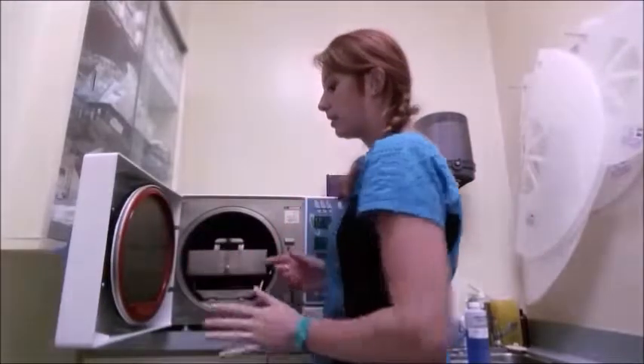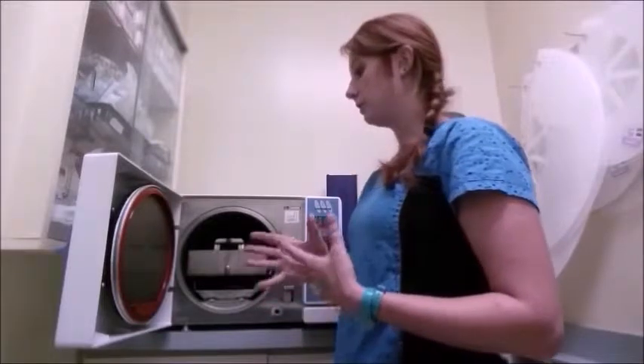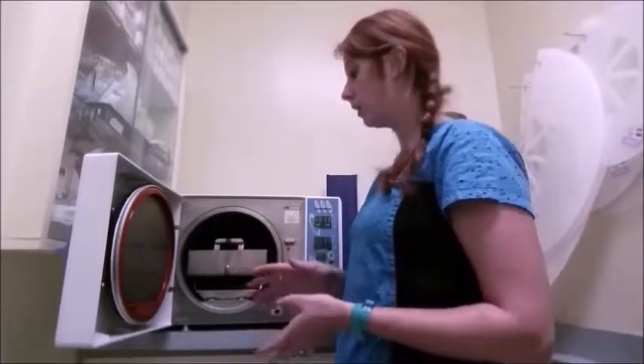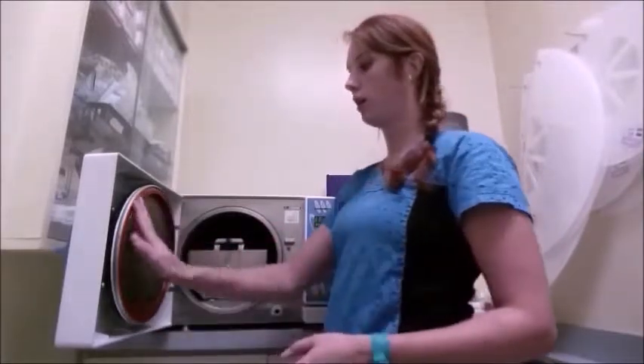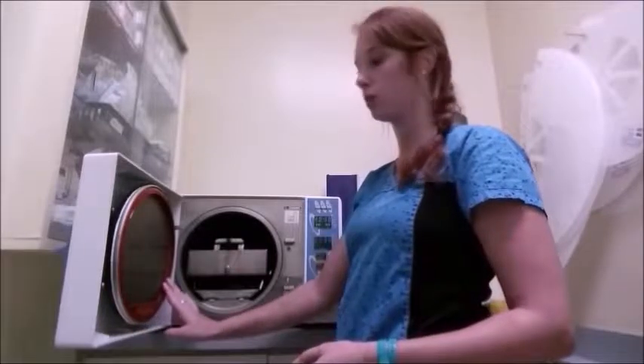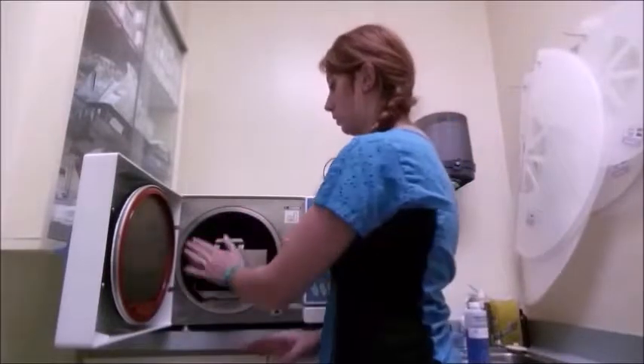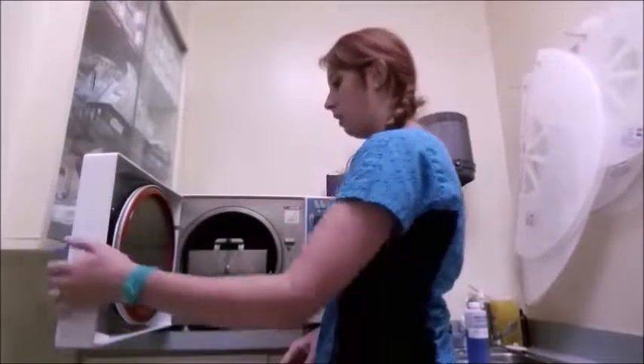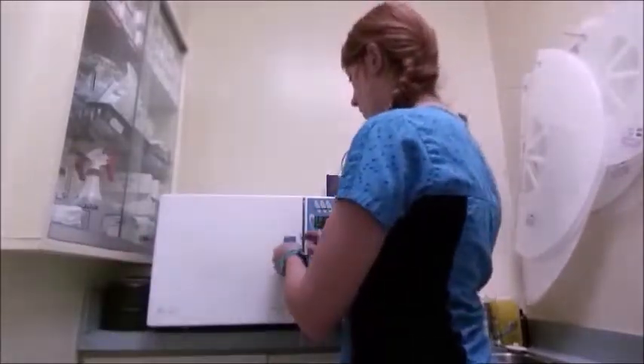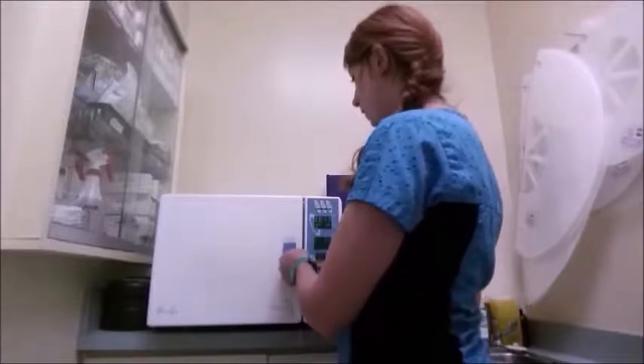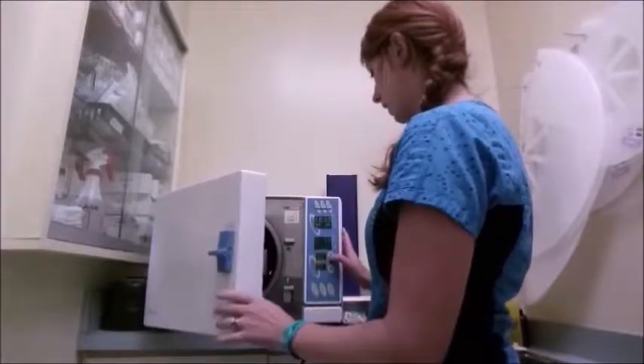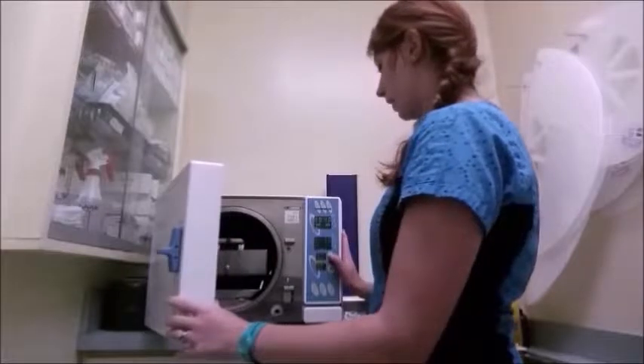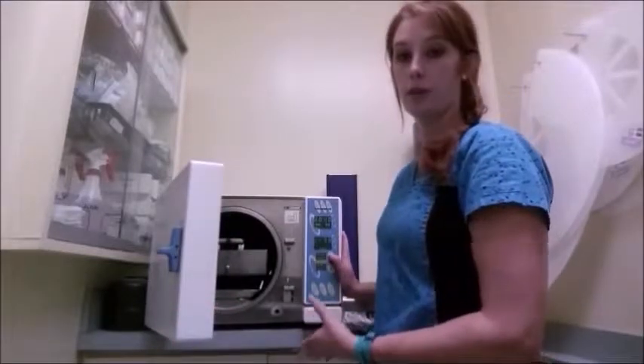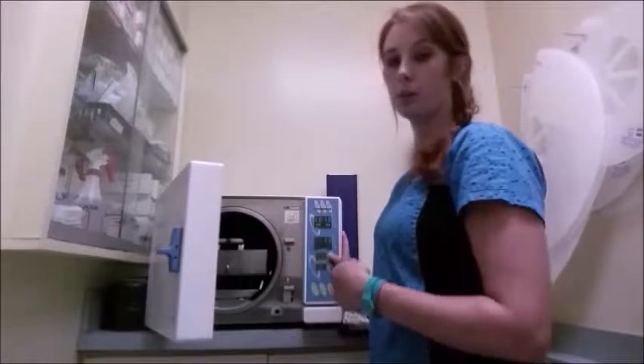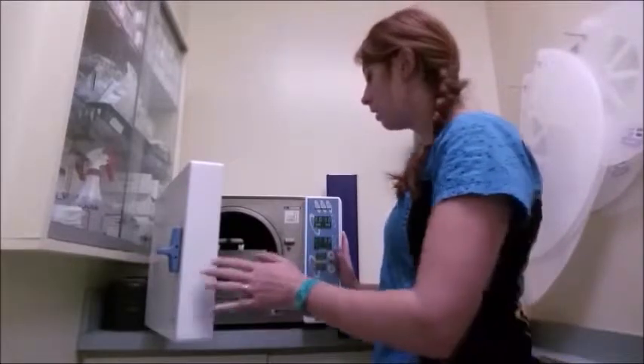For maintenance of our autoclave unit, we can do several things. On a weekly basis, we should be checking a couple of things. We want to check our door gasket and make sure that it's nice and clean. We can also clean off our boiler ring. We also want to ensure that our door latch is functioning properly. We can also do a test to make sure that the cycle should not run if the door latch is not closed and locked appropriately. An alarm will go off for that.